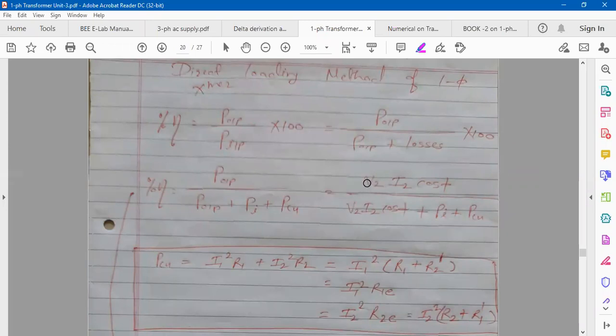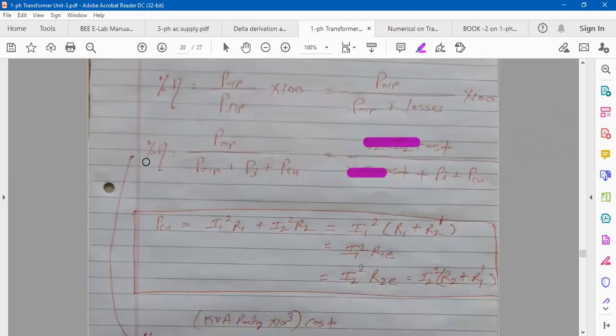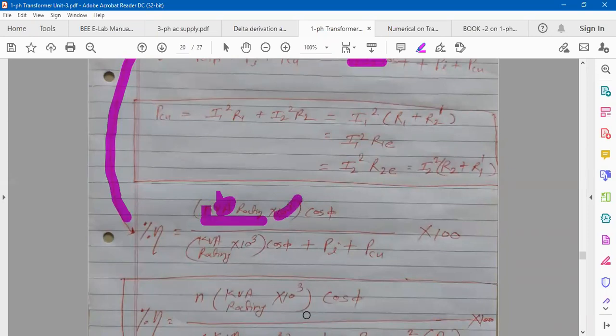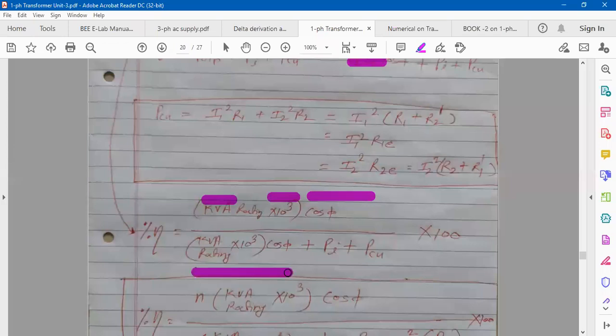If you look at the numerator, V2·I2 is the KVA rating. So you can replace V2·I2 with KVA rating in this formula. The percentage efficiency formula becomes: KVA rating — V2·I2 means volt-amperes — and if I write KVA, then it's into 10 to the power 3. So V2·I2·cosφ2 divided by the same parameter plus iron loss plus copper loss, into 100.